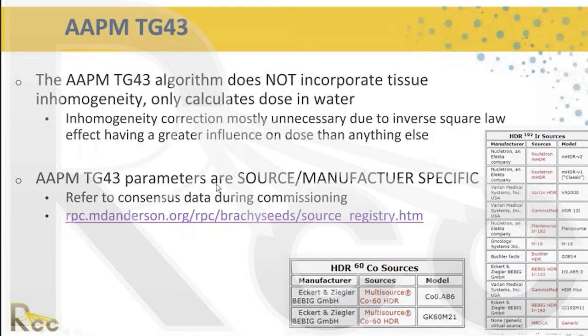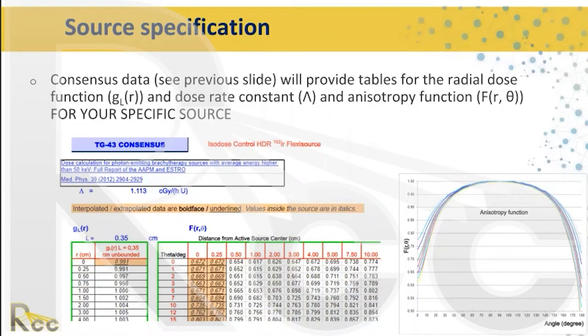All TG-43 parameters are source and manufacturer specific, generated either by the manufacturer or through consensus. Each manufacturer, when developing a new source, collaborates with multiple academic institutions to measure and model results, combining data from all institutions to establish consensus source parameters — which is what you see in the TG-43 report. If there are any questions, we are encouraged to contact the manufacturer directly.